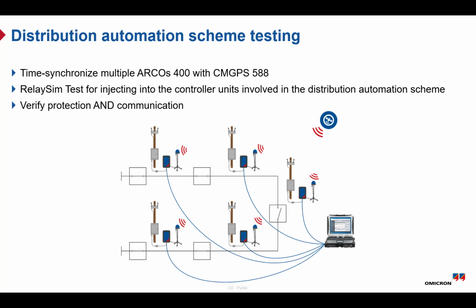By using multiple ARCO 400 units synchronized with a GPS device, we can inject signals at the same time into different controllers. This allows us to simulate real system conditions and verify both protection performance and communication. RelaySimTest software is used for this type of testing. It allows you to model the system using a single line diagram and simulate a realistic fault condition. The software then calculates the required signals and applies them to the connected devices. With this approach, you can test the entire protection schemes, not just individual devices, including switching logic and communication between controllers. It also allows control of multiple test sets from a single PC, making the process efficient and coordinated. So overall, this method provides a more complete and realistic way to test modern distribution automation systems.